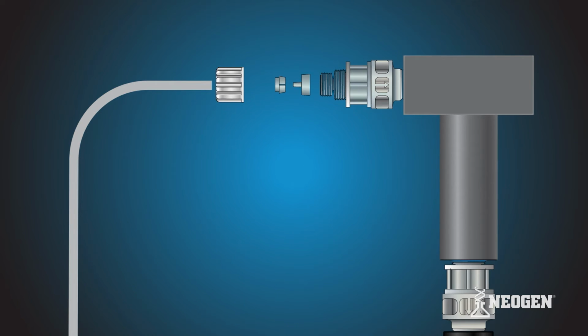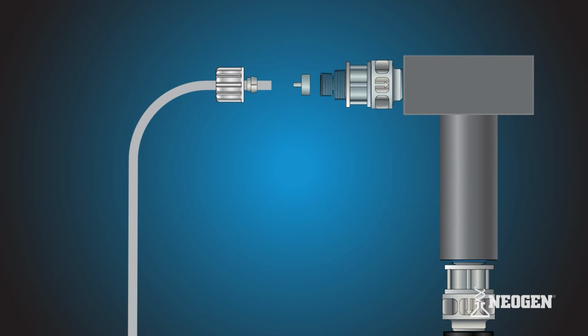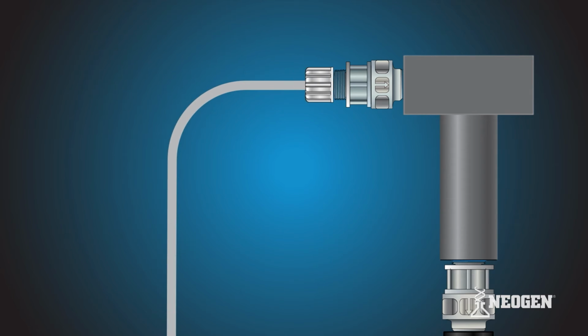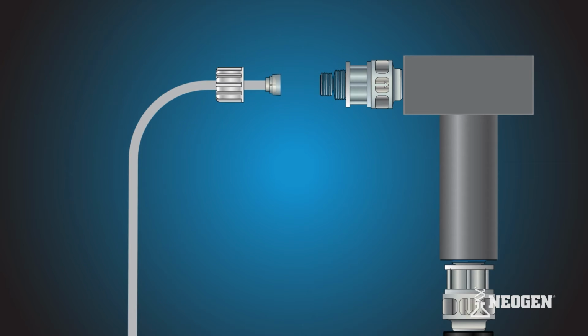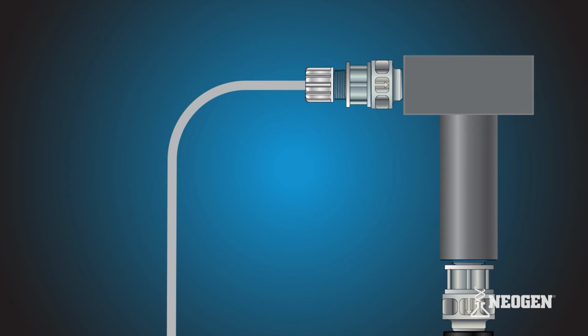Slide one end of the discharge tubing through the outside opening of the tube nut. Slide the collar onto the tube and make sure the collar's crown is pointing away from the tube nut. Grab the nozzle and insert the pointed end into the opening of the tube. Push the collar and nozzle together as close as possible. Attach the tube and tubing connections onto the injection valve by hand tightening the tube nut. Do not cross thread or over tighten. If the tube nut is not securing, recheck the ferrule connection.